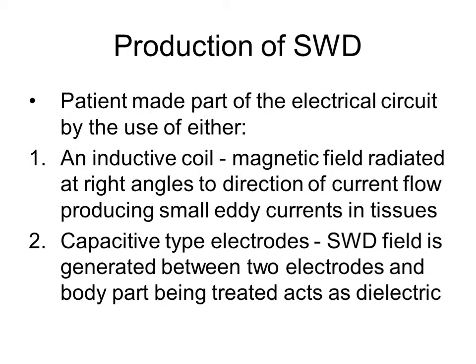There are two ways of applying shortwave diathermy, both of which are dependent upon making the patient an integral part of the electrical circuit. An inductive method involves the flow of electromagnetic energy through a coil. A magnetic field is set up at right angles to the coil, and it is this that creates small electrical currents in the tissues. In the past, this method involved wrapping the limb in an inductive coil, but more modern methods use a coil within a drum applied at right angles to the tissues. The capacitive method involves placing the tissue to be treated directly between two electrodes, and the body acts as a dielectric, completing this circuit and conducting the electromagnetic current from one electrode to the other.